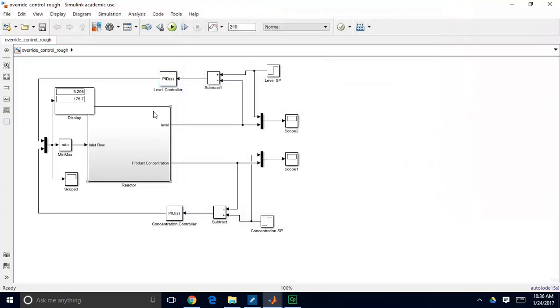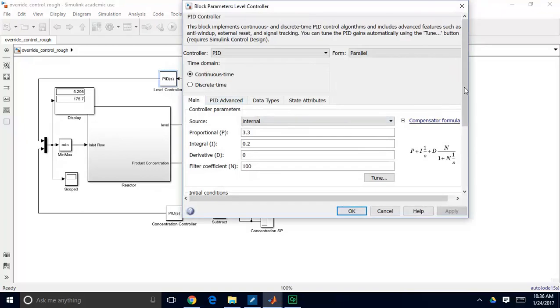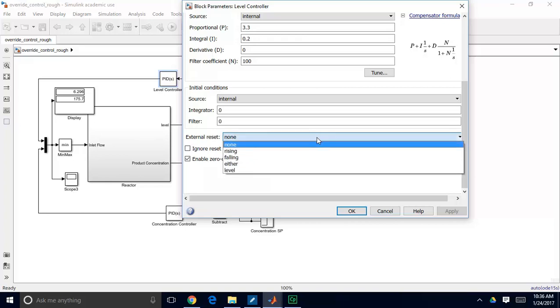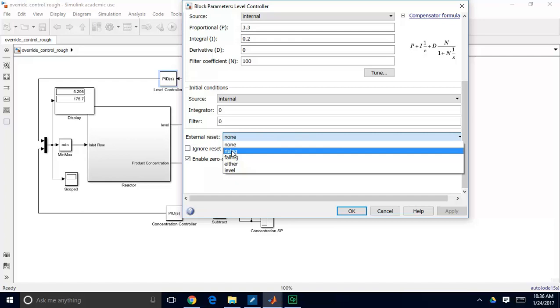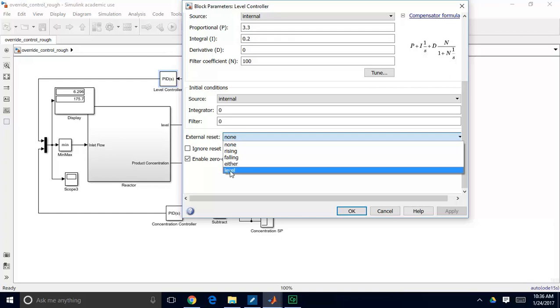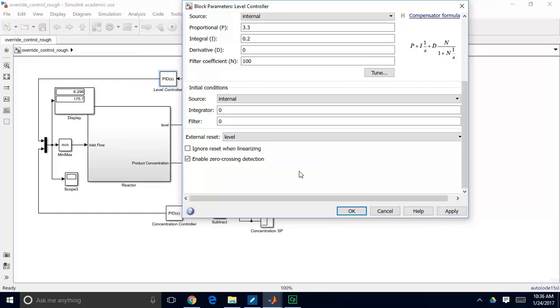So in this case, the way we're going to handle this is we're going to use a similar method, but we're going to go to our controller, and we're going to pick an option on external reset. So what external reset does is it allows your controller to receive an external signal, and that external signal is what will prevent it from integrating. So we have several options here. We can stop our integrator from integrating when there's an external signal that's rising or falling, or either rising or falling, or at some level. So we want to pick this level. So basically what this means is that when this external signal is non-zero, our PI controller will stop integrating.